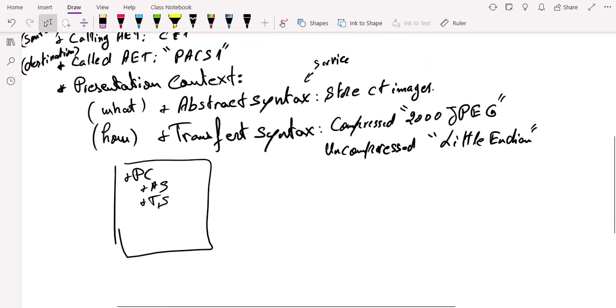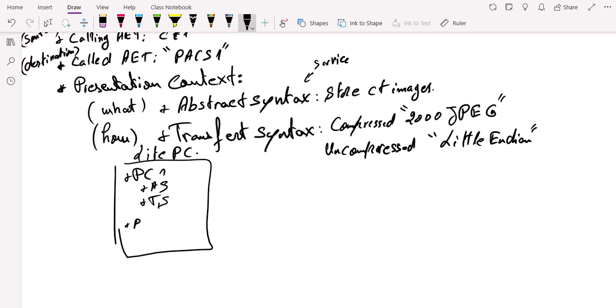So here, the CT scan will send all this information, including a list of presentation context, presentation context one, presentation context two, etc., until 128 presentation context. That's the maximum. And in this presentation context, we're going to find the services that we want to use, and the way we want data to be exchanged between the two systems. So in presentation context two, we're going to find abstract syntax and the list of transfer syntax.